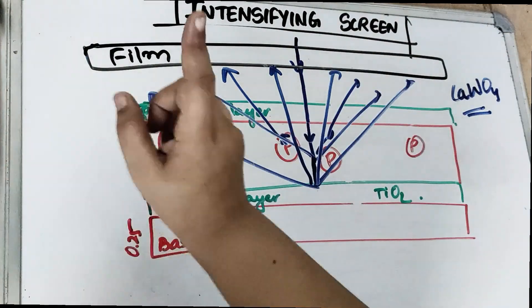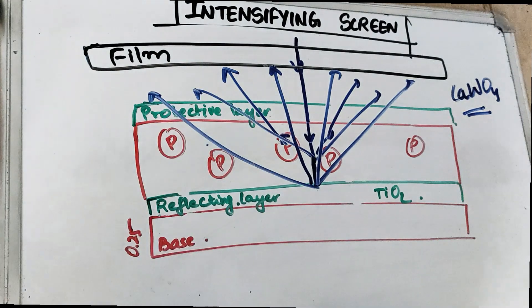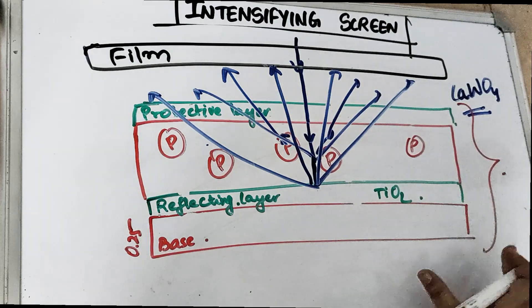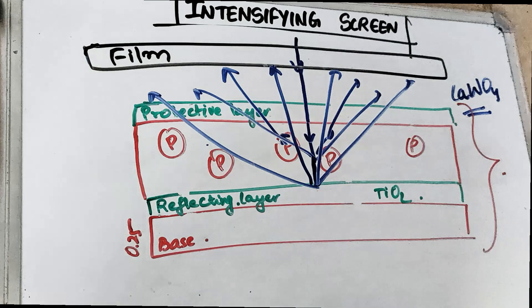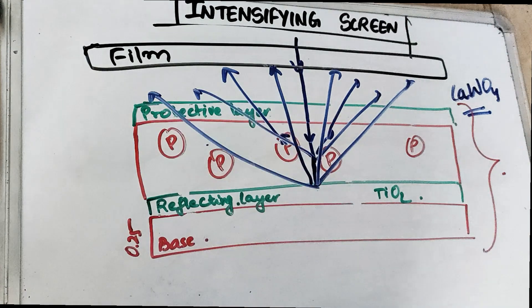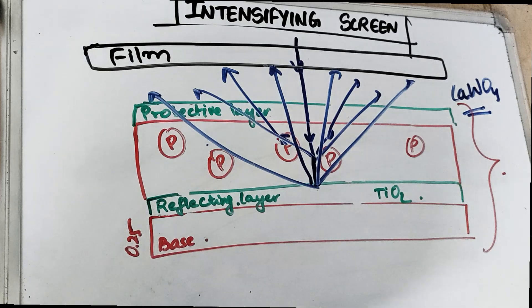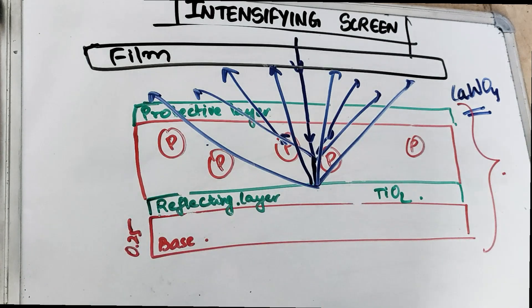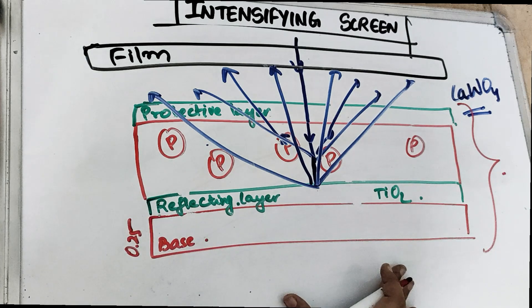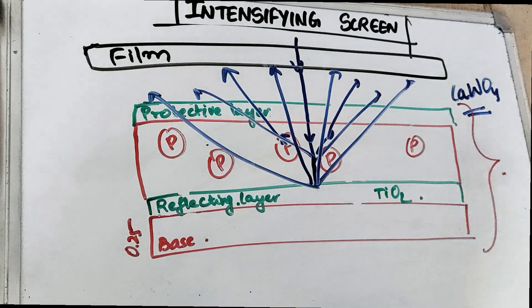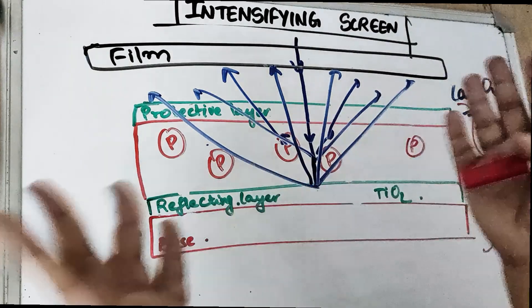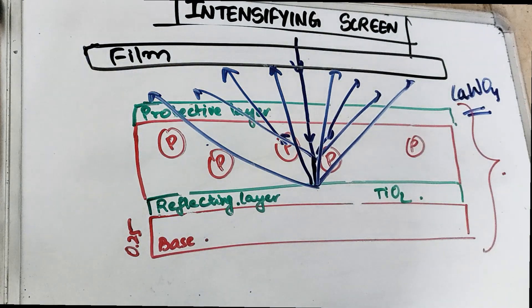This is the reason we do not use this intensifying screen in the IOPR. We use it for our extra-oral radiographs — for OPGs, for cephalograms, skull radiographs — all extra-oral x-rays and cephalometric radiographs. We use this intensifying screen for those. But here we have a catch — the calcium tungstate is scattering the light. We have something more recent: the rare earth intensifying screen.